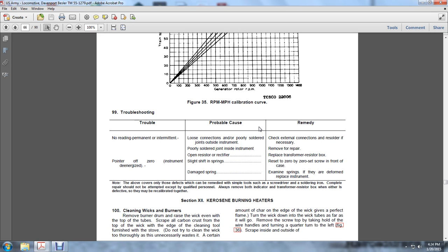Pointer off zero on instrument when de-energized: slight shift in the spring. Reset the zero with the set screw on the front of the case. Damaged springs: examine the springs, and if they are deformed, replace the instrument.